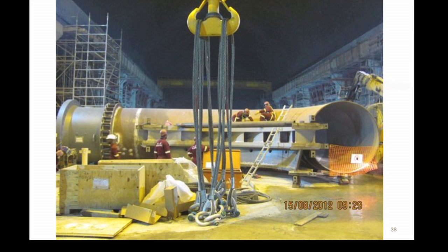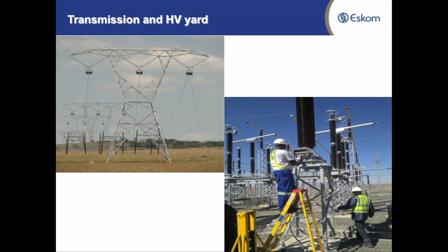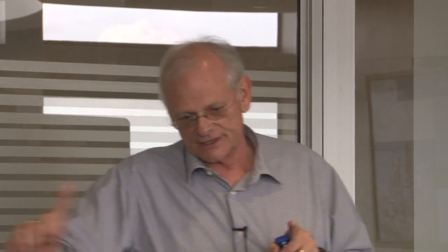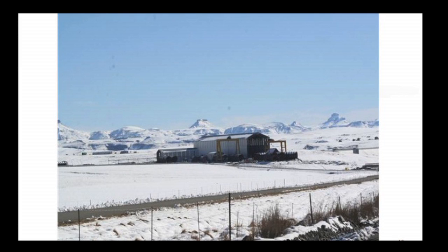That's then been welded on site. Then of course we had to take the power out, so we have 3 lines in pump storage of that sort of magnitude. We need to have a loop, and we need to have a redundant supply as well. So the loop gives you 2 lines, in and out, and then the third line is the independent line. And you won't see this, but that was this winter, the upper side, and this is my story. Thank you very much.